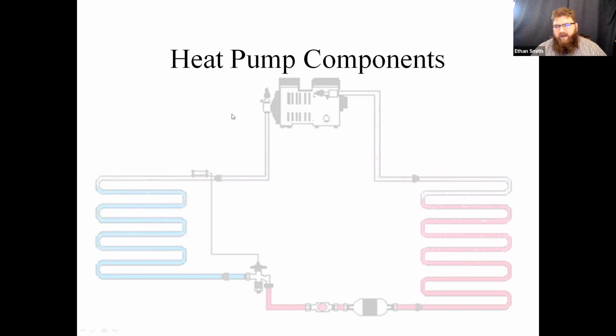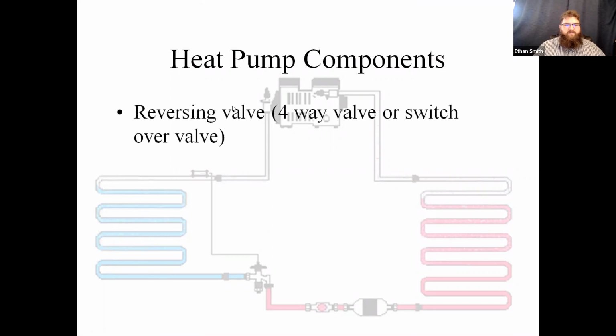So let's talk a little bit about heat pump components. So things that are unique to heat pump installations, guys. We're going to have a reversing valve. We've got to have some way to switch over from heating to cooling. So reversing valves are called a bunch of different things depending on whose equipment you're talking about, where you are in the country. Someone calls it a four-way valve, switchover valve, mode control valve, reversing valve. They're all the same thing. They're just a way to switch modes between heat and cooling. Okay. We're also going to have check valves in a heat pump system. We have to be able to ensure the refrigerant is moving in the correct direction. We do that by using check valves.